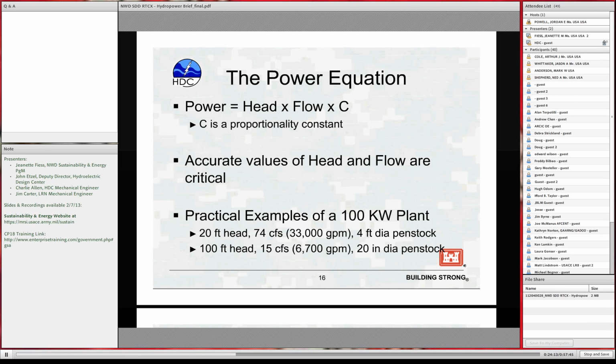And to give you a sense of the size that we're talking about, for a sample 100 kilowatt machine or power plant, if you have a 20-foot head, to get 100 kilowatts, you need 74 cubic feet per second or 33,000 gallons per minute. And to deliver the water to that at a reasonable velocity and reasonable conditions, you need a 4-foot diameter penstock.